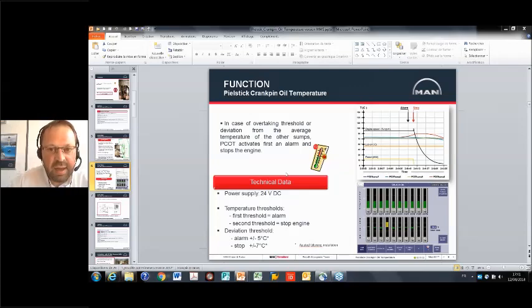It's not the same. SCADA is a complete supervision of the power plant; that's the standard name. Our system is not a SCADA, it's a complement to the existing one. If we decide to add some sensors or protection on your engine, we can put in an MMS cabinet, and this cabinet will send information to the existing SCADA. It depends on the level of your SCADA. Sometimes, on a project I have now, a power plant has no SCADA, just a manual indicator, so we install a computer with all the information from the MMS. That's already a lot - main bearing, exhaust gas, splash oil, speed sensor - it's a lot of information, but it depends on each case.